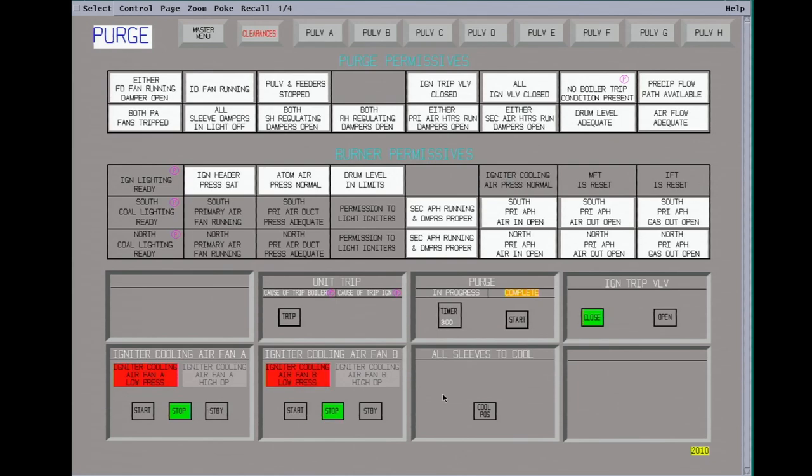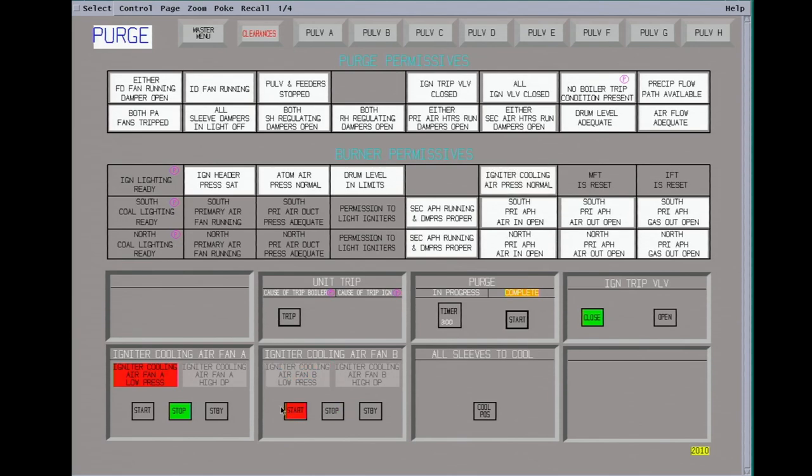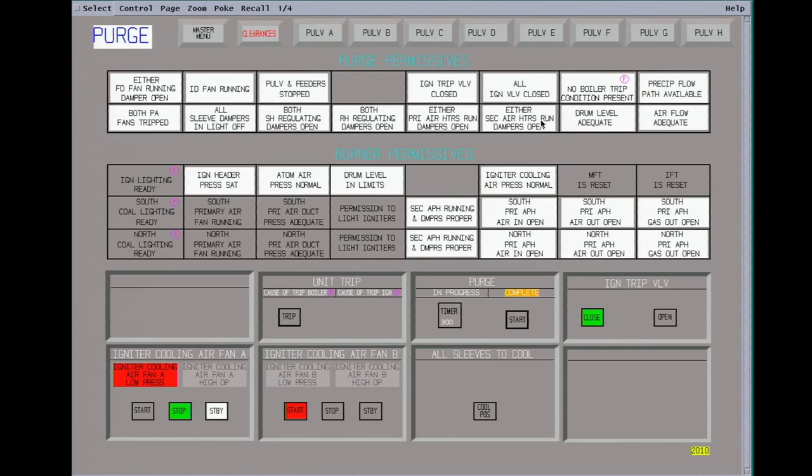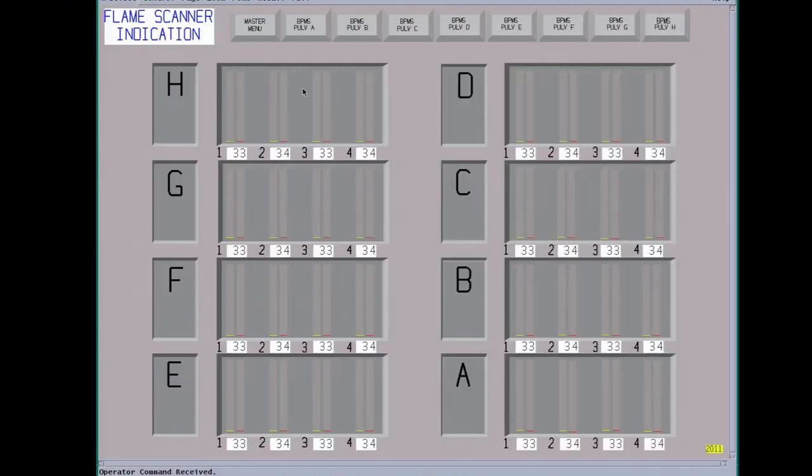Okay, our purge has completed. We timed out at 300 seconds, five minutes. We're going to start the igniter cooling air fan. This provides cooling air to the igniters and also the flame scanners. There is quite a bit of heat. Put the other fan in standby. One thing you always want to look at in plants is to make sure all your backup equipment is in standby. It's a good idea to go through all the screens before you really start the shift. Okay, all the purge permissives have been made. We go to the flame scanner. All our dampers are open.